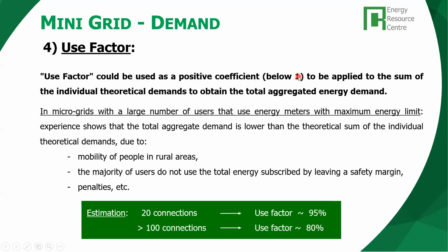So this is a factor below 1 that tells us how much of the contracted electricity is not going to be effectively used, okay? And we use these factors to reduce a little bit the sizing of the mini grid. This is especially important for mini grids that are a bit large. Of course, when you talk about mini grids with 50 families, 20 families, this is not much. You see, for 20 connections, the use factor is almost 1. But when we go above, when we consider larger mini grids, we can introduce reductions in the use factor. We can consider use factors of 80%, 70%, etc. Okay, so that is a factor we can use to reduce the sizing.